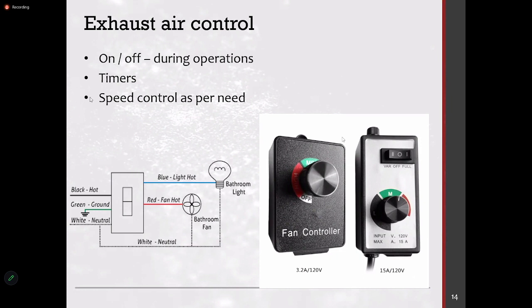Yeah, and exhaust air can be timer driven as well. Things like toilet exhaust. Most of the time what you do is you couple it with the light. So whenever somebody switches on the light to move in, the fan actually runs. But this is okay for a medium traffic operation. But generally, if it is high traffic, we recommend to go with timers.